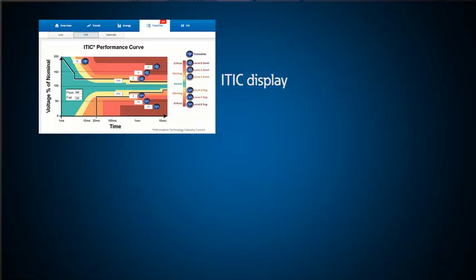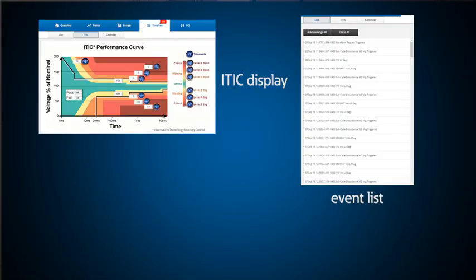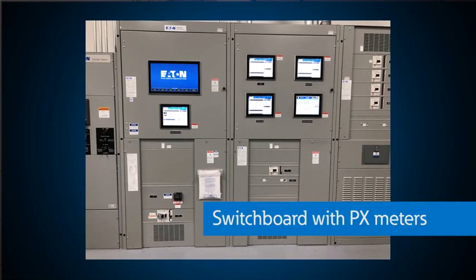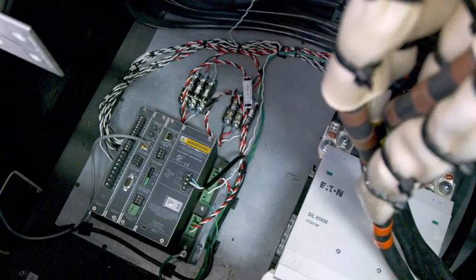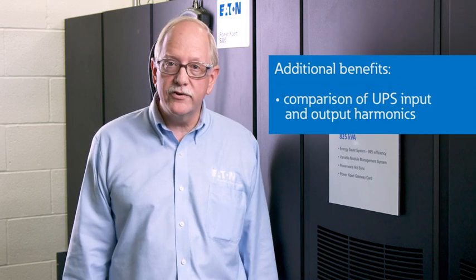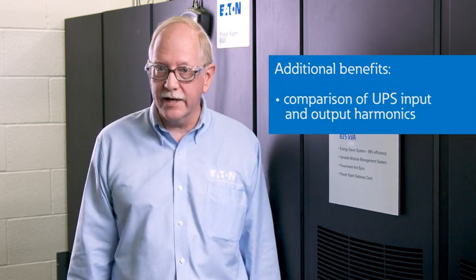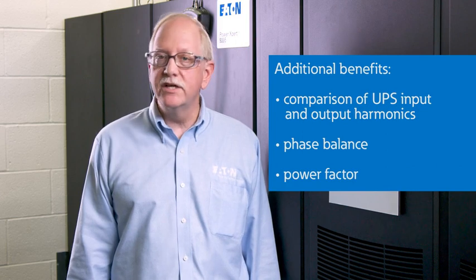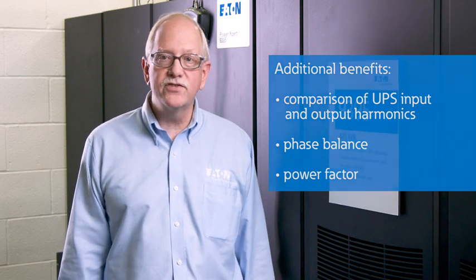As described previously, we can select events for viewing based on the ITIC curve display, the event list, or the event calendar. The power expert meter can be installed in the switchboard or switchgear associated with the UPS, and in some cases the meter may be located inside the UPS I/O area. The PX meters also offer other benefits including the comparison of UPS input and output voltage and current harmonics, phase balance, and power factor. This ensures that the UPS is doing its job conditioning the power, providing isolation from harmonics, and not just acting as a battery in a box.